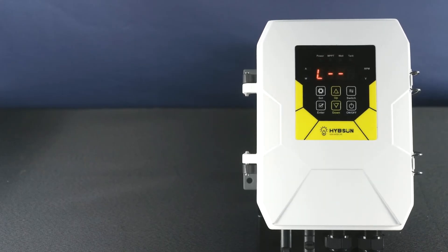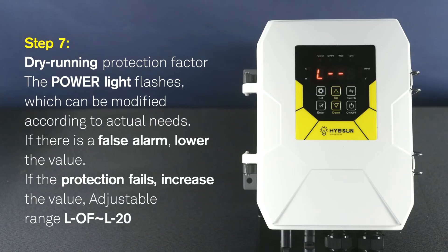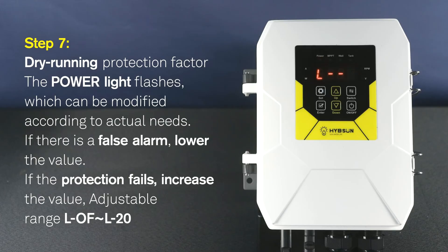Step 7: Dry running protection factor. The power light flashes, which can be modified according to actual needs. If there is a false alarm, lower the value. If the protection fails, increase the value. Adjustable range: L0 to L20.